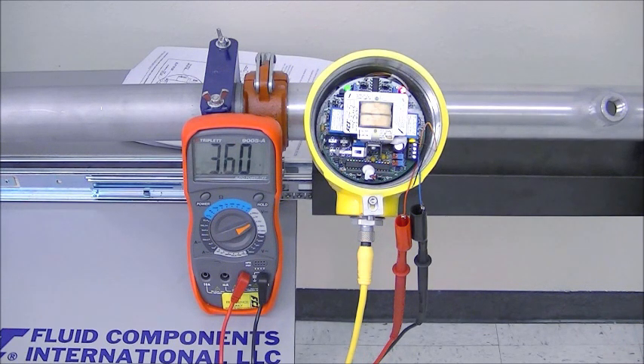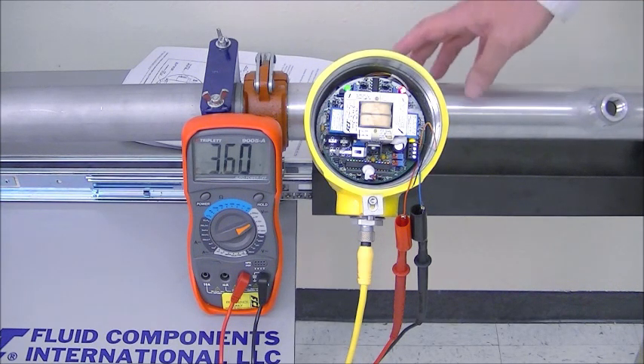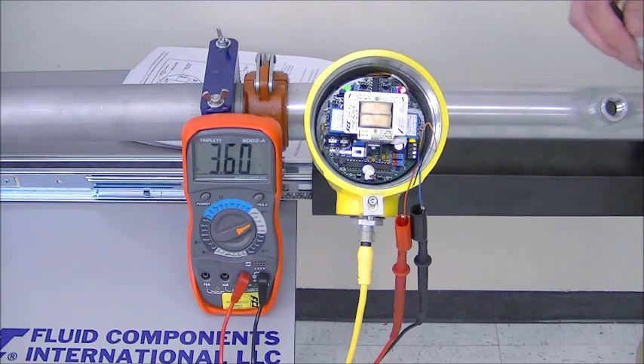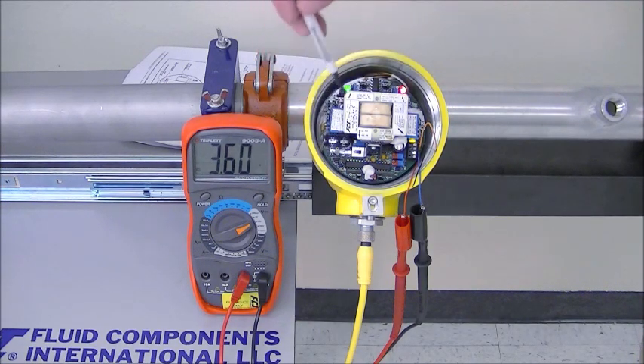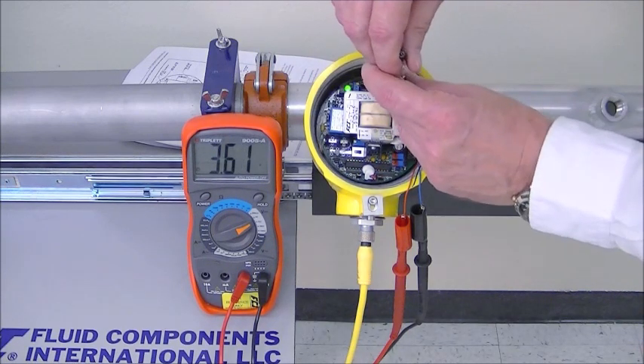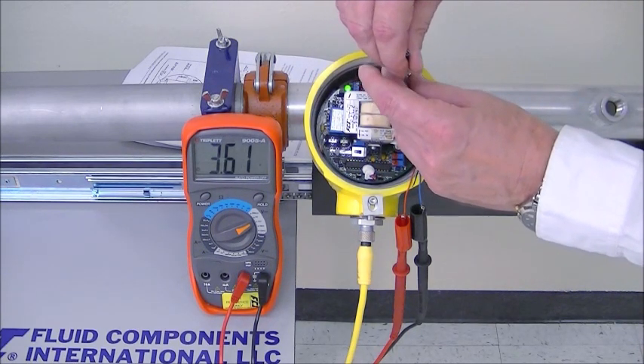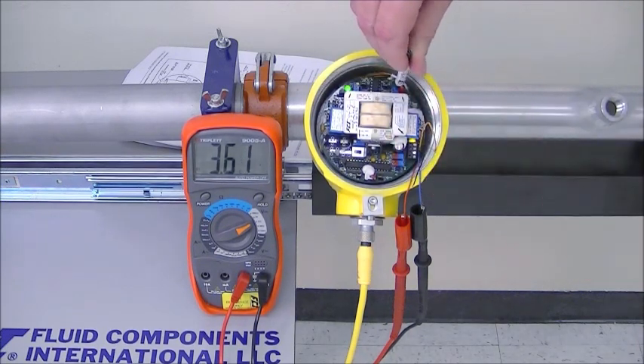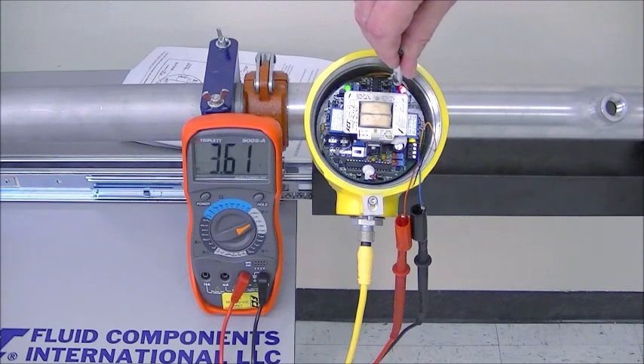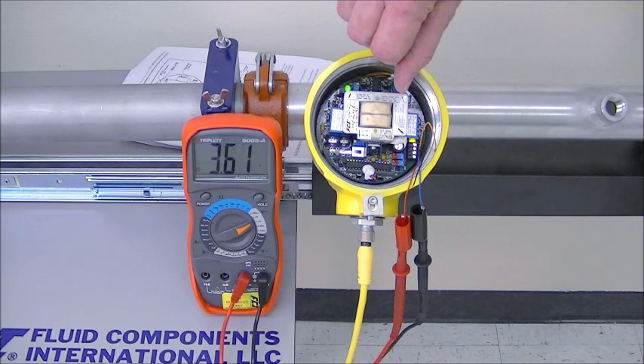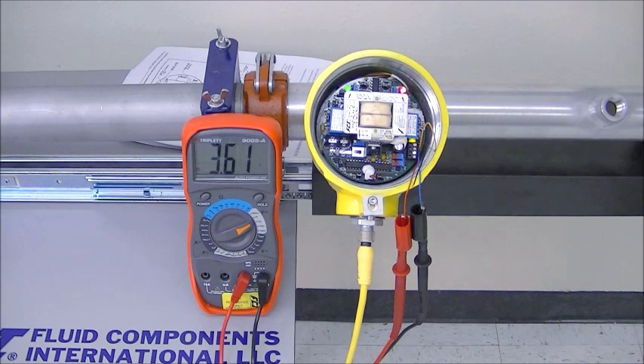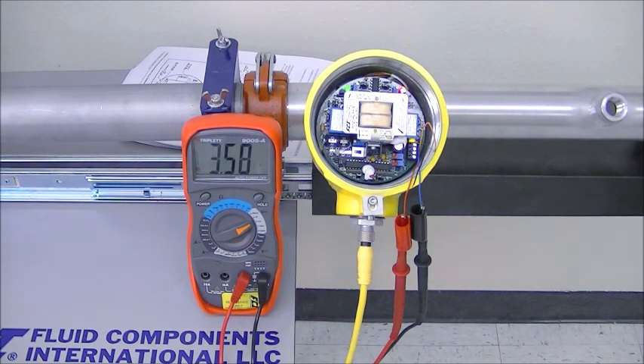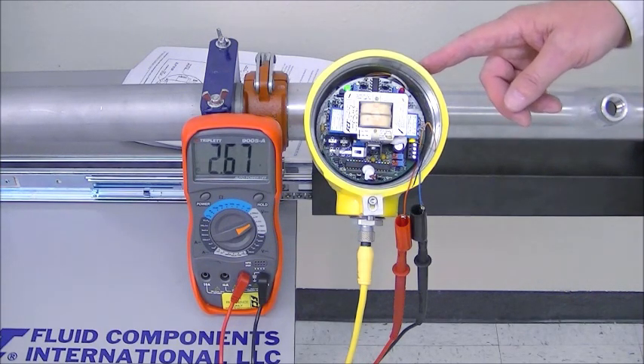However, if you want to optimize a set point, for example, going from no flow to flow, what you do is you install the switch in a pipe that has no flow. And you leave the switch in a run mode and you simply turn the set pot for relay number one, in this case, until the relay just comes on and then you turn it an extra half turn. Now, if we turn the flow on, see how quickly it goes off? You get a very fast alarm.